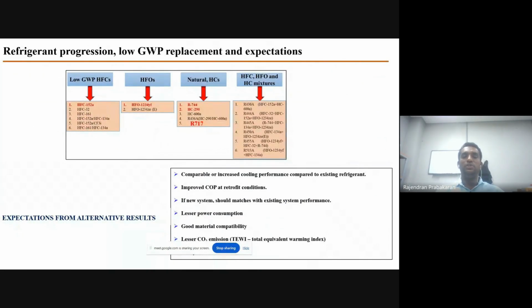So these are all the low GWP refrigerant replacements and expectations. Under low GWP HFCs, we can see that R32 and R152a are the frontrunners. In HFOs, R1234ze, R1233zd and R1234yf are the frontrunners. And among natural refrigerants and HCs, R290 and R717 are the frontrunners in the building sector. But R744, a CO2 refrigerant, usually performs well under heating conditions rather than cooling conditions, and it also has transcritical and subcritical cycles compared to other refrigerants because of its very low critical temperature.